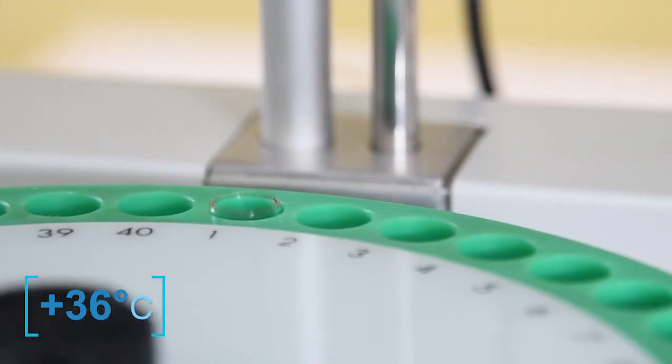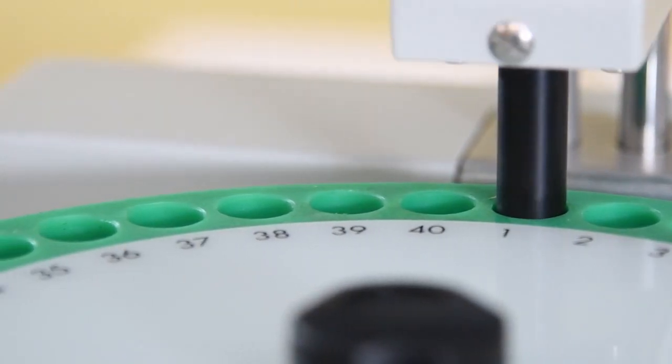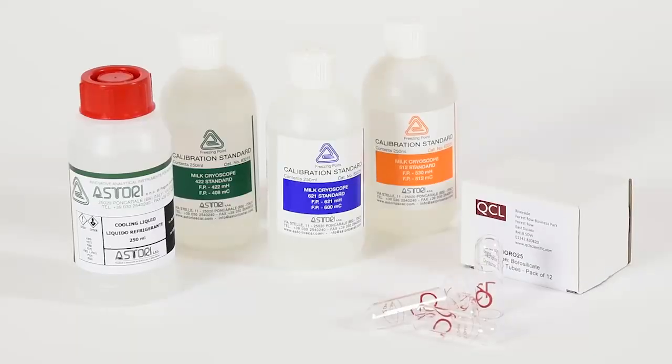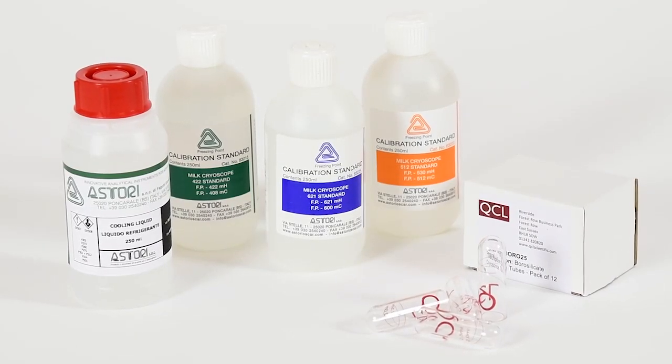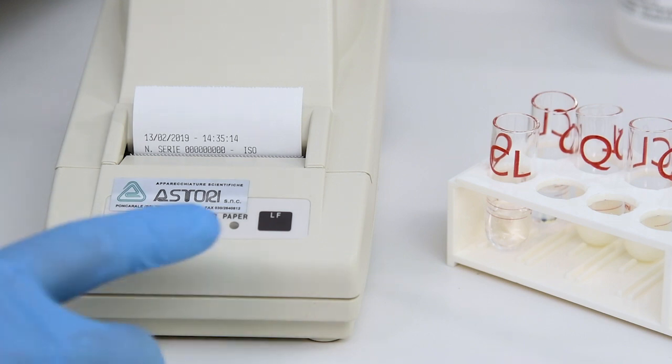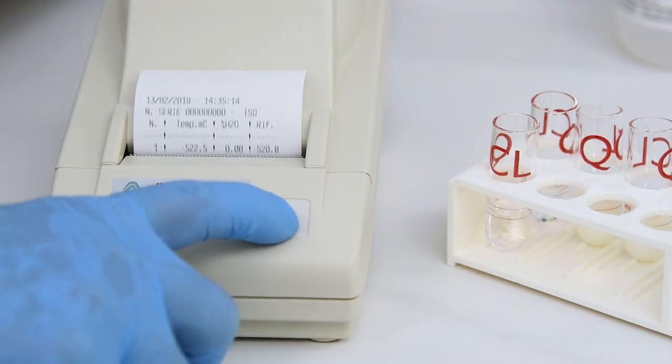They can work with room temperatures up to 36 degrees Celsius. All consumables, such as the calibrated glass tubes, the certified calibration solutions, and the cooling liquid are in full compliance with ISO 5764 2009 standard, in order to ensure unquestionable test results.